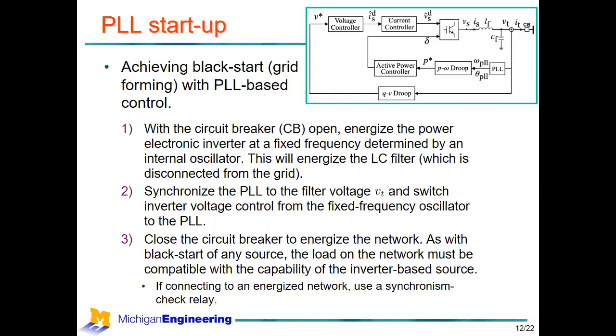So there's a circuit breaker, which connects to either the grid or whatever the load is that's being supplied. With the circuit breaker open, I energize the power electronic inverter using some fixed frequency. So for this initial part of the process, I'm just energizing the inverter. It's connected to a filter. Where you see that L sub F, that's the inductor and its capacitor. When I energize the inverter, it's going to energize the filter and apply a voltage at the point V sub T. So I'll energize the filter. I have a voltage there.